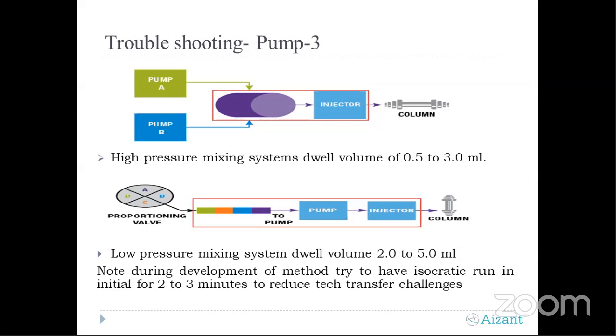So there is a challenge when you do the tech transfer of your method. Whatever make of HPLC we are using, whether it's a high pressure mixing system or a low pressure mixing system, we have to check it. And if you know the method is having a challenge with respect to dwell volume, during method development we should take care to make the initial 2 to 3 minutes isocratic. This will resolve your issue of changing retention time when you do the tech transfer to other sites.